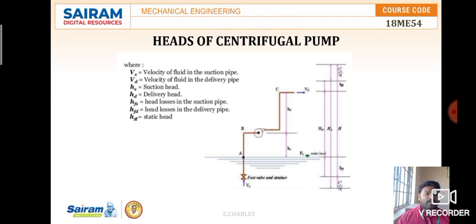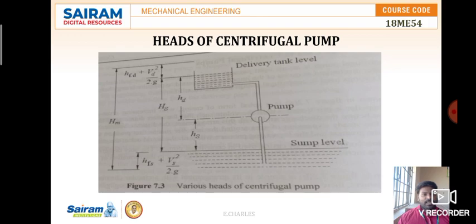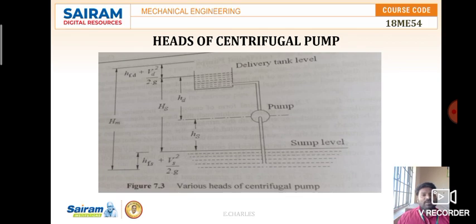Looking at the heads of a centrifugal pump: the portion from the suction level to the eye of the impeller is the suction head hs. There is a sump level where the suction pipe is immersed, and a delivery pipe fixed to an overhead tank. From the eye of the impeller to the delivery tank level is the delivery head hd. The combination hs plus hd gives the total static head.